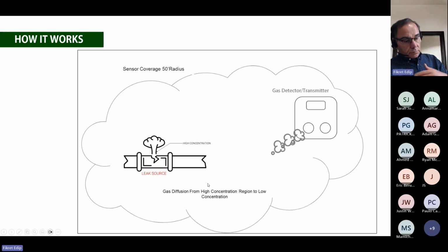Now, I was asked a lot of times, you say your sensors cover a 50 feet radius. That's huge. How does it work? The way the sensor detects gas is on the diffusion method. Imagine we have a gas leak here. At the source of the leak, you have a high concentration. With the air movement, it's a natural physics thing that the high concentration transfers over to the lower concentration of the gas. So with natural diffusion and air movement, before you know it, this reaches the sensor, detects the gas, and then sends a signal to the controller and activates the alarm.